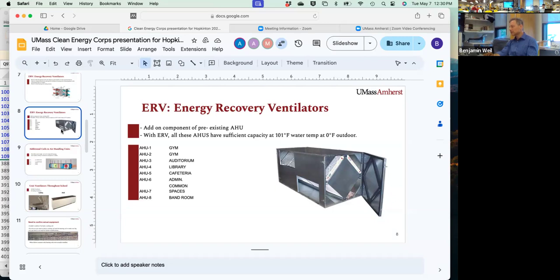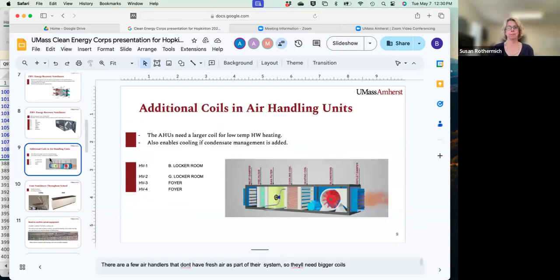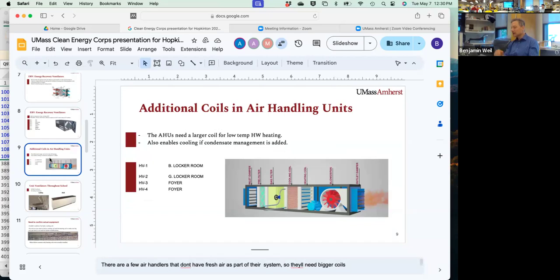But you'd only do that if you're sure that you're keeping the air handling units, otherwise you specify a new air handling unit. Yep. Same with this. If the air handling units don't have any fresh air, you could specify a new coil that's rated for 105 degrees. It will therefore also be a cooling coil if you provide condensate management. You may decide you don't need cooling in the locker room and the foyer, in which case you don't bother with the condensate. You also have to decide, do I want to keep this air handling? So that's a separate decision that I don't think we were capable of helping you figure out. To our eyes, things seemed like they were in great shape and didn't need replacing.